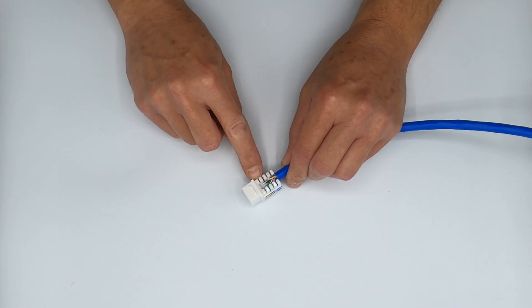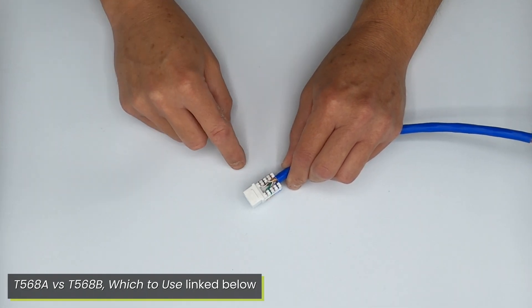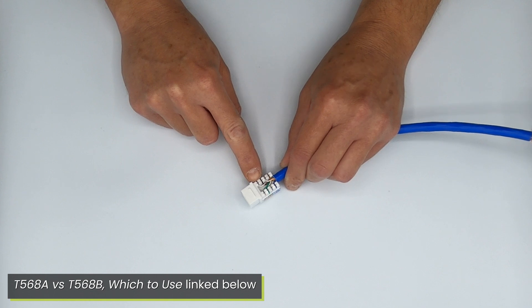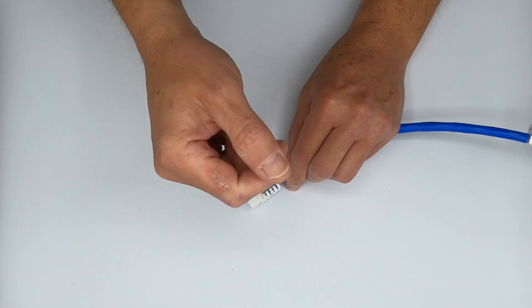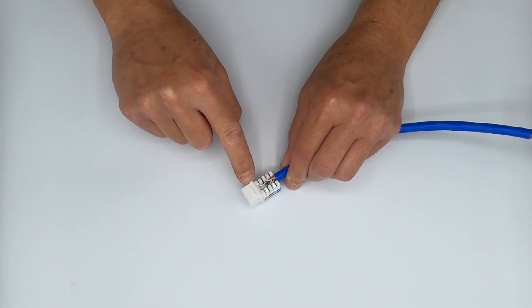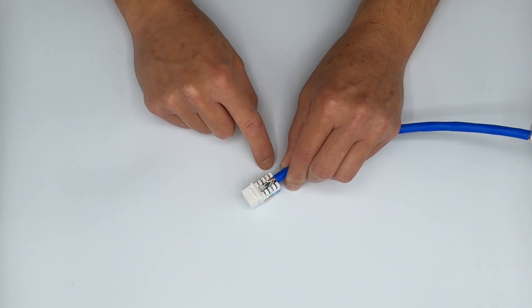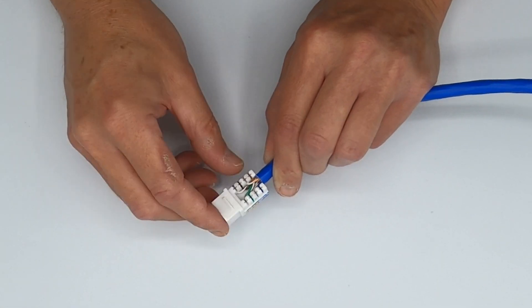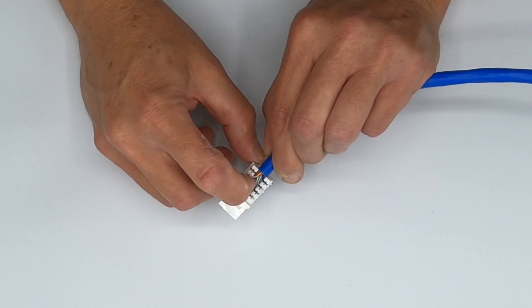There's another video that discusses the differences between those, but this jack I have punched down the wires into each of these slots. And the rules are the same - half inch. It doesn't matter whether we're talking about a plug or a jack.